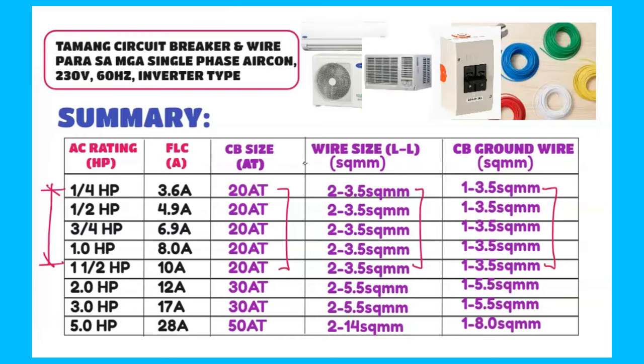Okay? So, next is from 2 HP to 3 HP. So, ang circuit breaker na dapat gamitin is 30 ampere trip. Yung wire size is dalawang 5.5 square mm. Ang size ng ground wire is isang 5.5 square mm. And then itong 5.0, so lumalabas na 50 ampere trip yung required circuit breaker. Wire size line to line is dalawang 14 square mm. Saka yung ground wire isang 8.0 square mm. So ganon mag-size up ng circuit breaker at saka wire sa single phase na aircon.